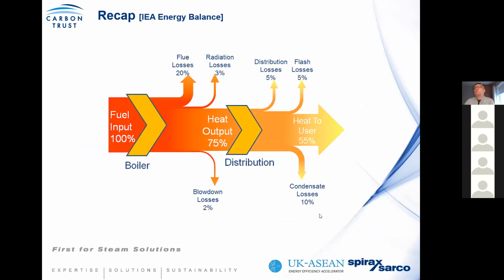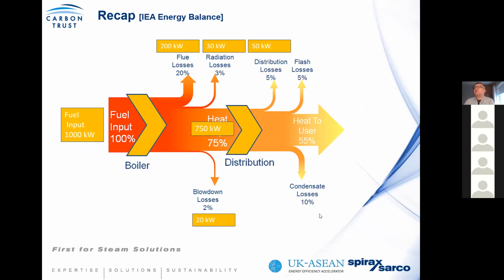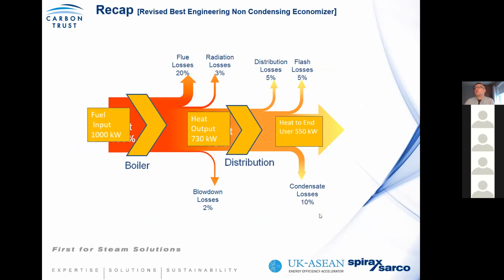So we're back to where we started. You can see again 100% of your energy input, and about 55% of your energy output. And you can see that for a megawatt in, these are the relative losses as per the IEA system. So we're only generating about 750 kilowatts of steam, and the losses are accounted for within the process conversion. Now, let's look at the points we discussed. Again, we started with every 1,000 kilowatts in. So your flue gas losses: you can look at economizers. And again, although a lot of you might have economizers, it's the mode of level control.